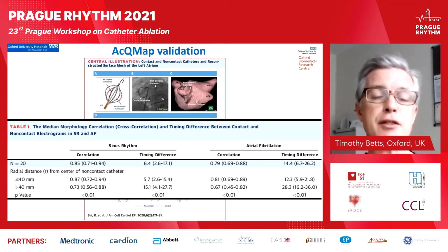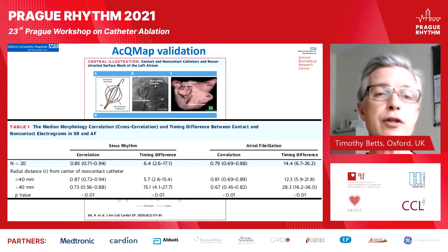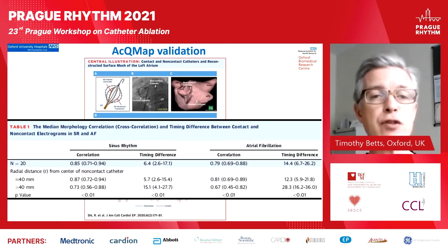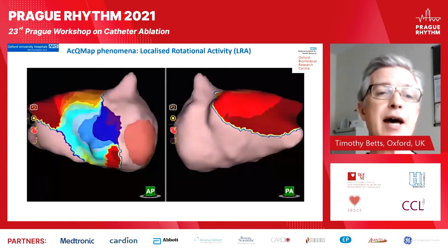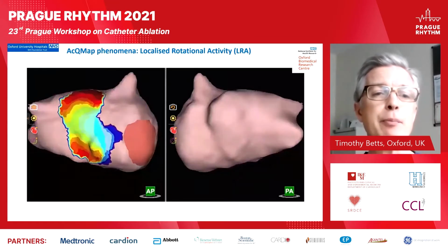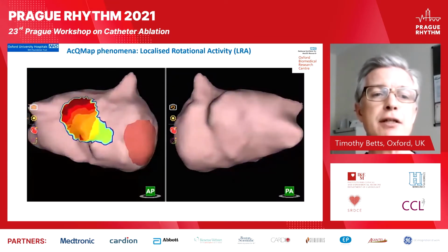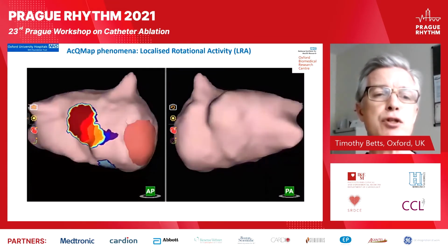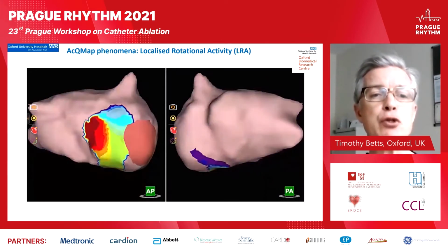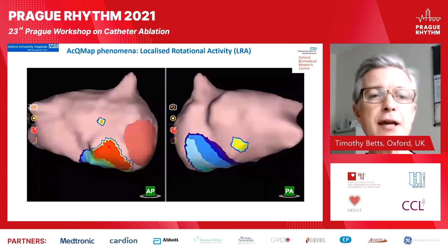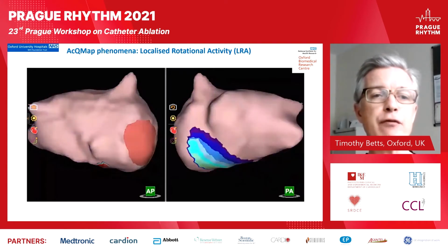It is somewhat distance dependent, and if you get more than 4 centimeters from the wall of the chamber, the resolution drops off. But with it positioned in the center of the chamber, it's very rare for that to happen. Now, when the propagation maps are calculated, this is the sort of thing which you would see played back at a slow sweep speed. So this is the left atrium in an AP and a PA view.